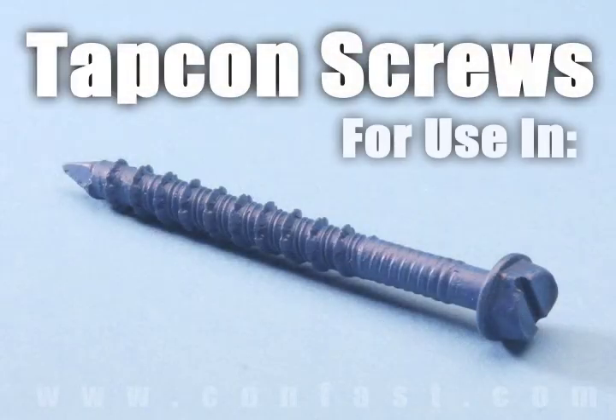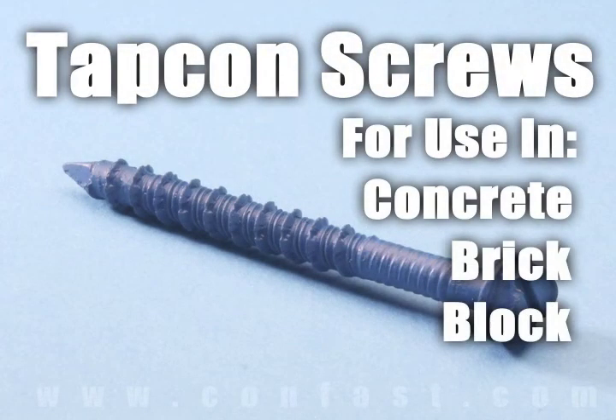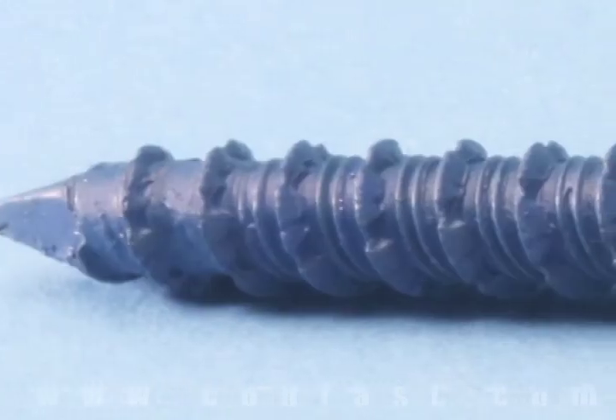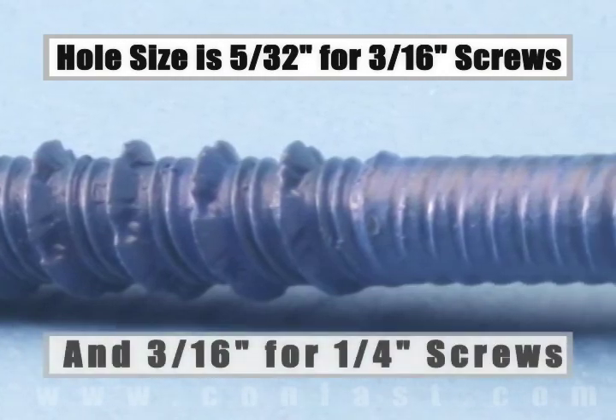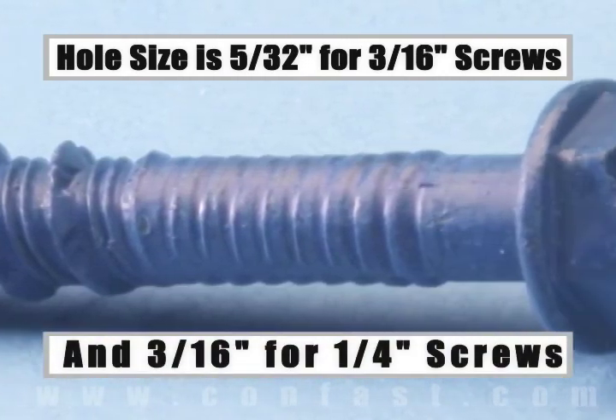Tapcon screws are designed for use in concrete, brick, or block base material. The size of the hole to be drilled is 5/32 of an inch for a 3/16 inch diameter screw, and 3/16 of an inch for a quarter inch diameter screw.